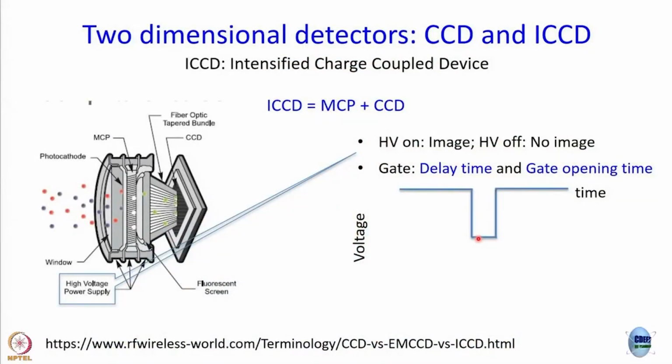Okay, but even before getting there, I want to record a fluorescence decay. How will I get it? Hit the sample with a pulse, right, and wait for whatever amount of time you want, open the gate for some time and then close it again, you make a measurement. In the next shot, fire the laser pulse, wait for some more time, open the gate for equal amount of time. In the same experiment, if you open the gate for different amounts of time, then it is going to be completely messed up. So, you have to define your gate time and you have to define the delays. You have to define the range of delays, right.